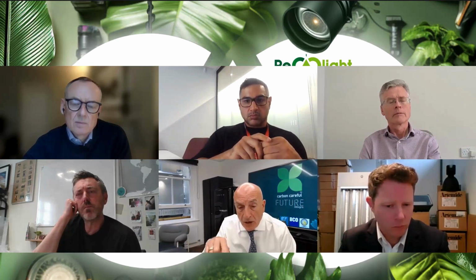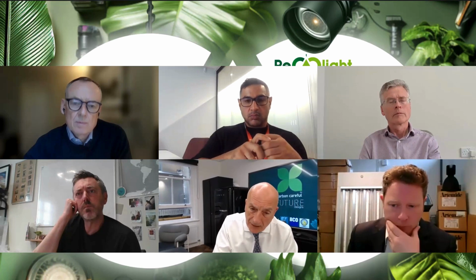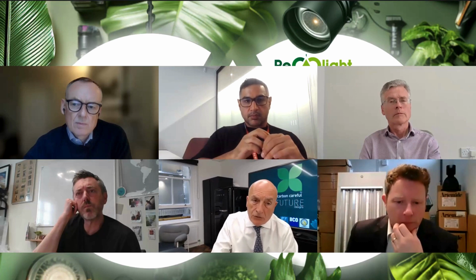But something Simon mentioned earlier, he said about reducing the quantity of products. Sometimes that's a good way of reduction. But from a layout point of view, generally where we do a lot, they say no, we want the same number, but we'd rather you turn the dimming down by 30-40% to reduce the lumen output, to keep the correct level. If they want their average 400 across the desk, that's what we can give them. So there's never been an occasion where we haven't achieved at least the light levels of the existing with LED, because it is just so much more efficient and more suited to lighting downward. That's what it's built to do.